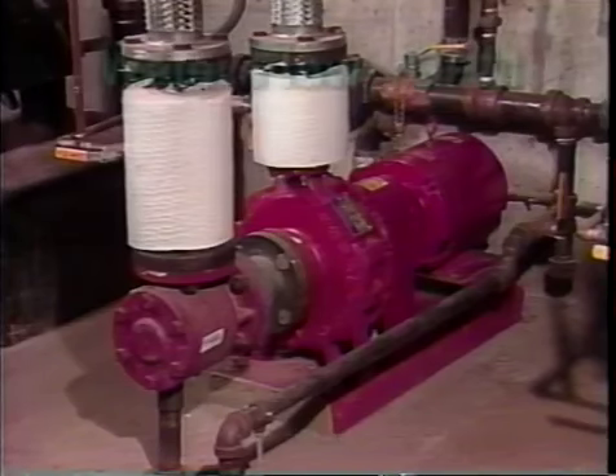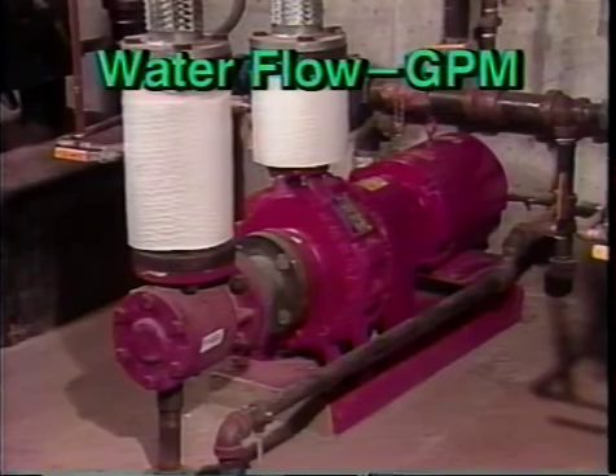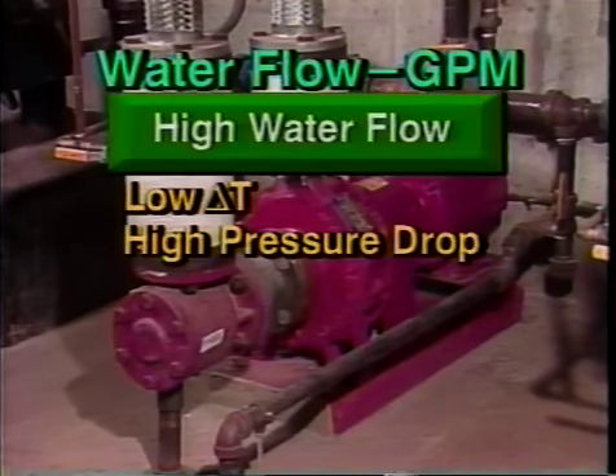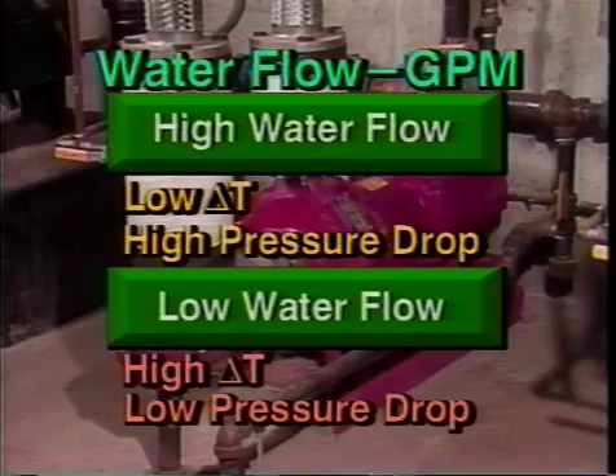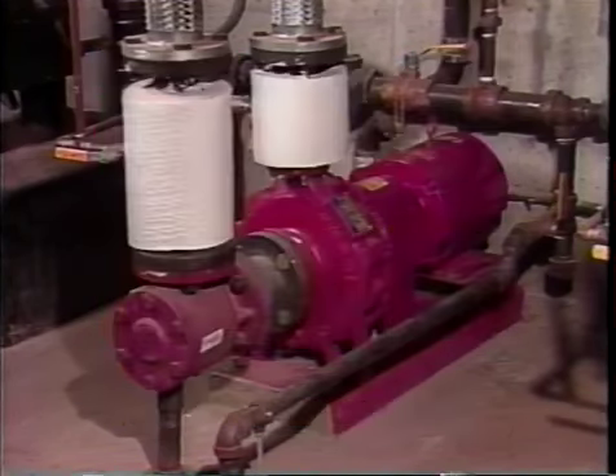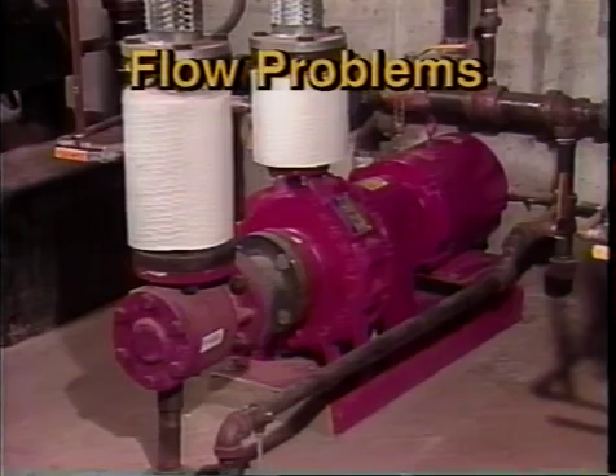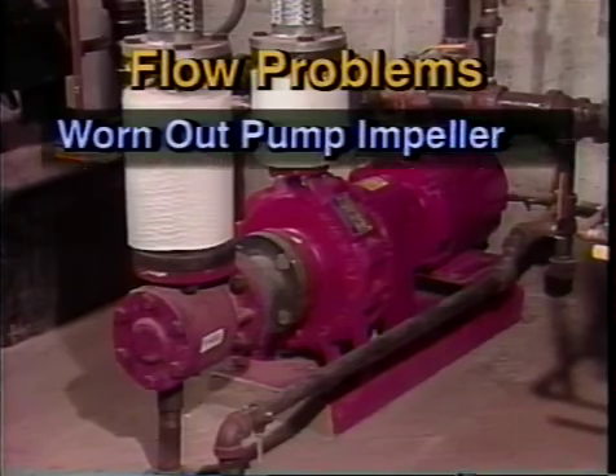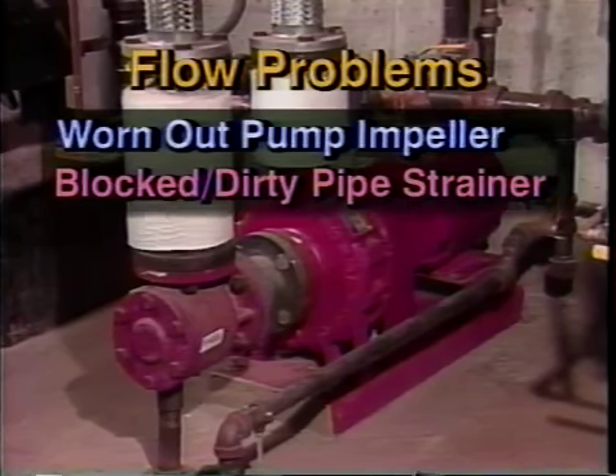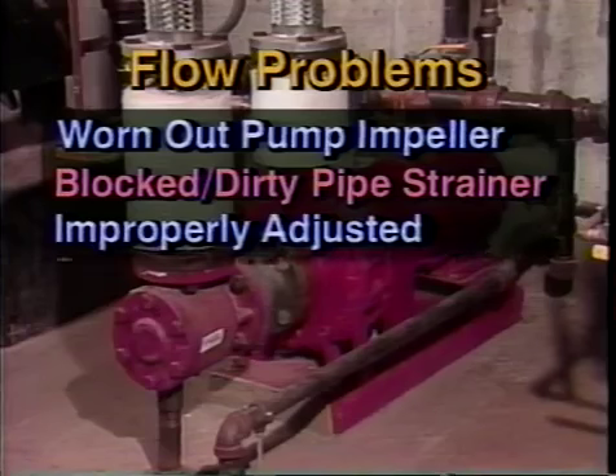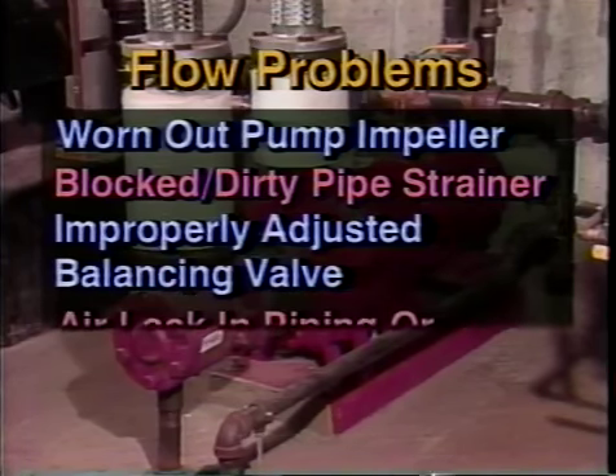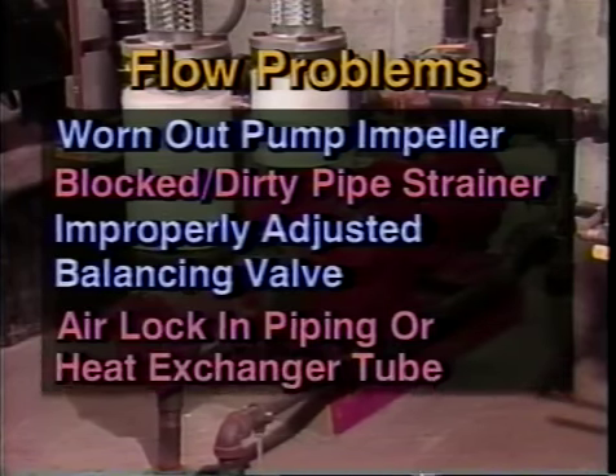If there are problems with the water flow, the conditions will look like this. High flow equals a low delta T and a high pressure drop. Low flow equals a high delta T and a low pressure drop. Flow problems can be caused by a worn-out pump impeller, a blocked or dirty pipe strainer, an improperly adjusted balancing valve, airlock in the piping or heat exchanger tube bundles.